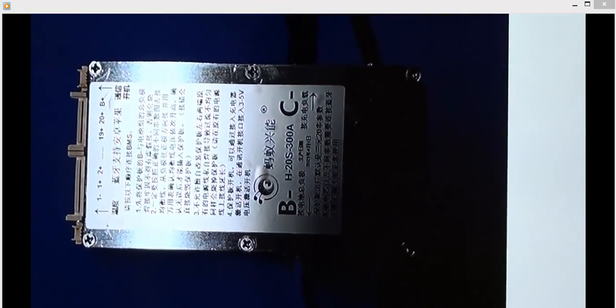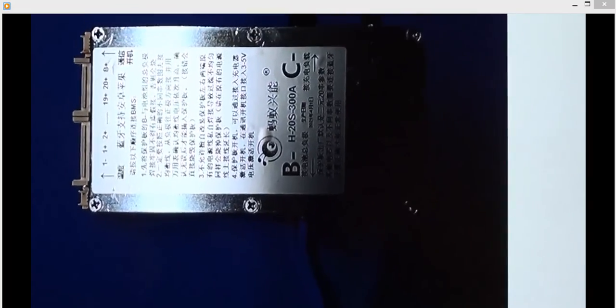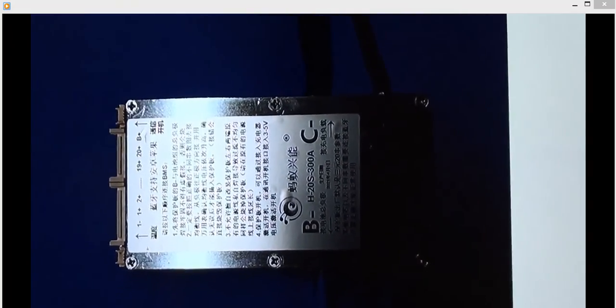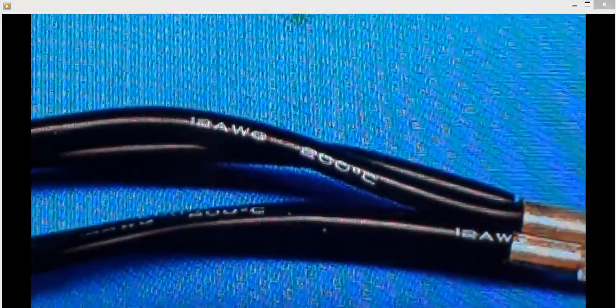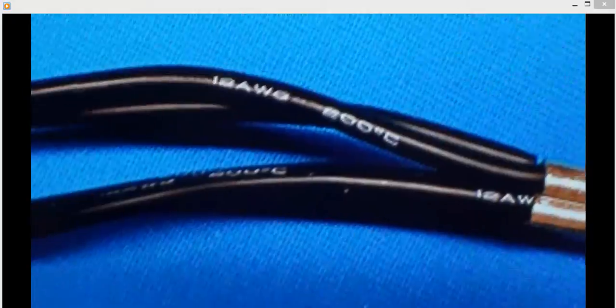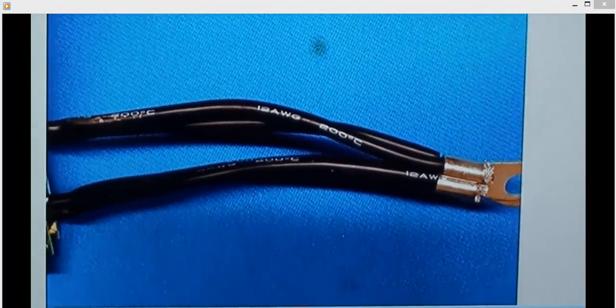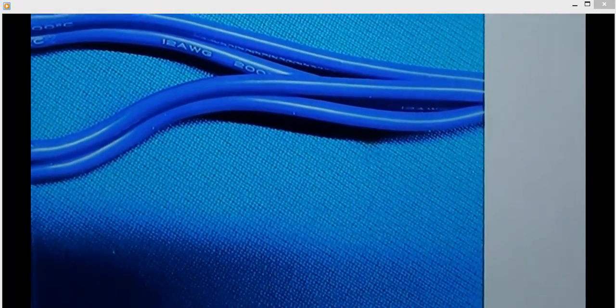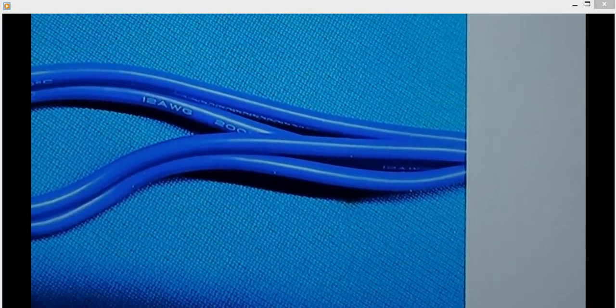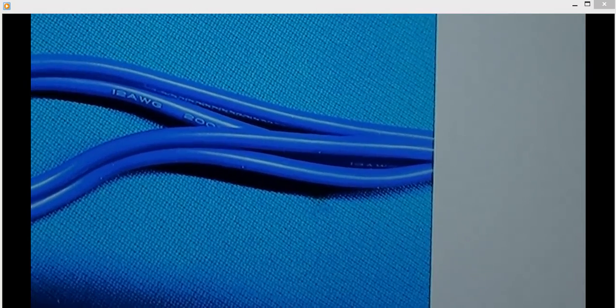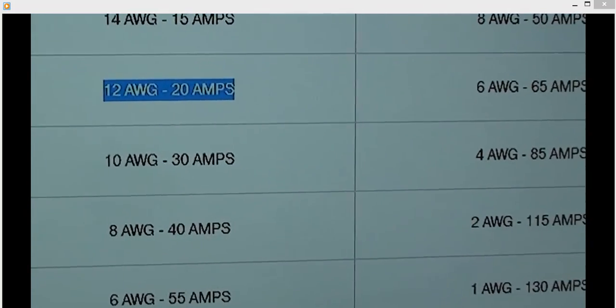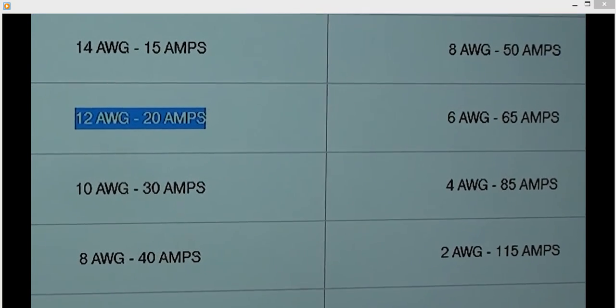And there's a closer view of the sticker. But when we look at the wires, there are 12 AWG. There's 4 of them, 4 black wires on the one side, and 4 12 AWG wires on the blue side. Now if we look at the 12 AWG, it's only rated at 20 amps.